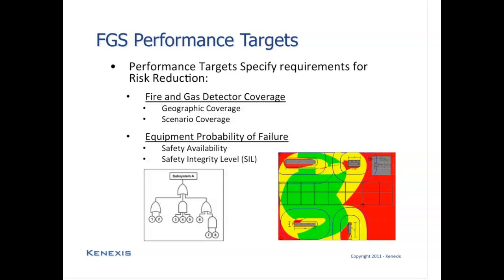And that coverage is usually presented in terms of a color-coded map in addition to tabular results. The color-coded map might, for instance, have red where no detectors can see the fire, yellow where only one detector can see the fire, and green where two or more detectors can see the fire. That visual map will then also be supplemented with tables where the coverage is calculated in terms of percentages of the floor space that have no coverage, one coverage, or two or more coverage.